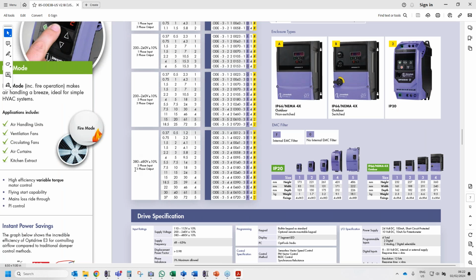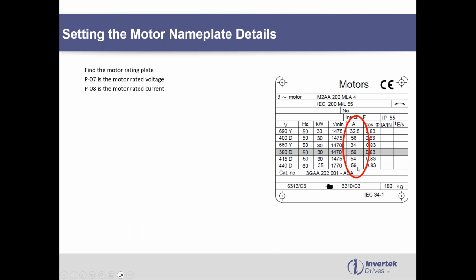So we just go into the brochure. This is the 400 volt range drive, so it covers from 380 all the way up to 480. And there's a 30 kilowatt or a 61 amp drive. So 61 amp all the way up to 480. That's no problems there. Like here, there's 59 amp, but it says it's 35 kilowatt. This is why I always tell people size the drive on the motor rated current, because the current is a real number, the kilowatts are calculated.